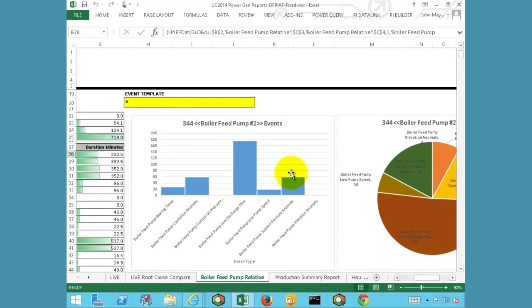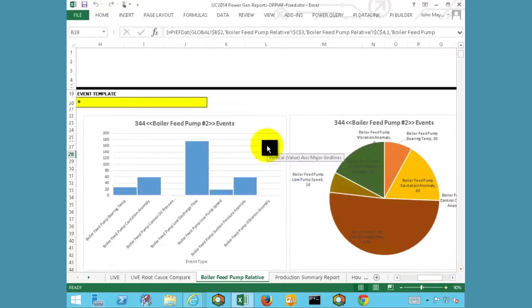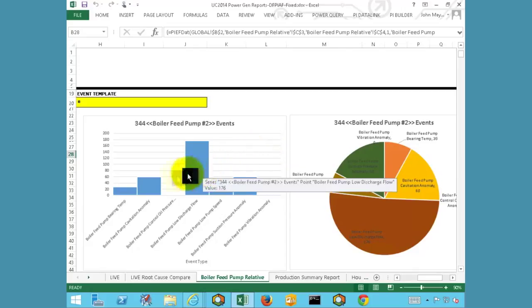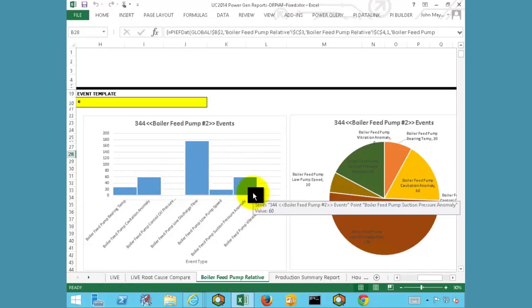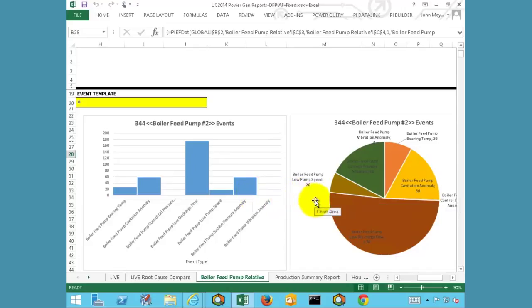For this report, we have created some charts that quickly summarize the overall health of our selected asset. These two charts can be used to provide a very quick overview of how the boiler feed pump has been operating over the past month. A low number of events would indicate that everything was fine with the equipment and that we could refrain from creating a maintenance event. However, in this situation, we can see that there have indeed been numerous events: discharge flows, cavitation anomalies, bearing temperature, pressure anomalies — all of which might indicate that a visual inspection or work order would be warranted.